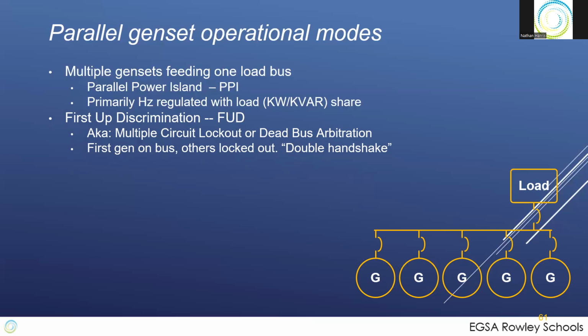The first one comes on the bus, it says, I'm ready to go on. It looks at the bus and says, the bus is 0 voltage, I'm going on the bus, close my breaker. Well, the problem we run into is that some of these generators would come online and be almost ready at exactly the same time. They both look at the bus and see no voltage and close their breaker at the same time, out of phase with each other, and bang, one of them's going to lose and come down, maybe both of them. So now we've employed this FUD, this first up discrimination, also called multiple circuit lockout or dead bus arbitration, different terms for the same thing.